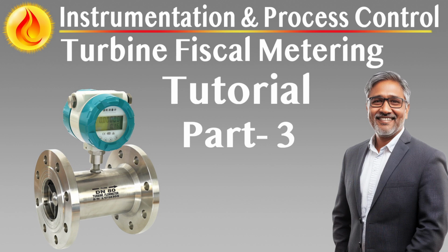Differential pressure monitoring must be installed across the strainer to detect fouling and signal the need for cleaning. This may be accomplished through analog transmitters, pressure switches, or digital sensors interfaced with the control system. Alarms must be generated when differential pressure exceeds predefined thresholds, preventing bypass or performance degradation of the turbine meter due to flow obstruction. Strainer housings and internal components must be rated for full design pressure and temperature and constructed from materials compatible with the process fluid. Internal surfaces should be smooth and free of corrosion traps to minimize pressure drop and ensure ease of cleaning.